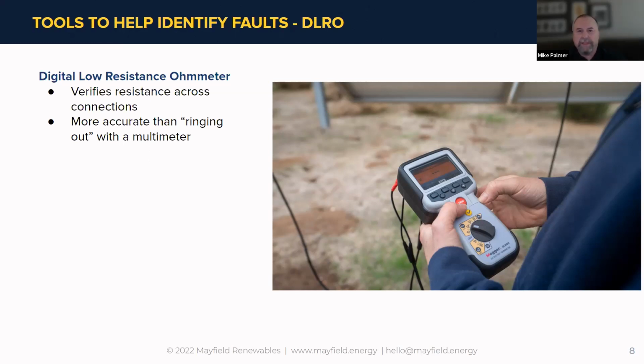And at the end of the day, it's really safety as well. But the other thing that affects these connections, I mentioned it earlier with the dissimilar metals, but we have temperature, we have the corrosion that occurs. We've pretty much hit it all on what the low resistance test will do. But there again, we have 2 amps, 10 amps, 100 amps, 200 amps, up to 600 amps. We're not using that, of course, on such small connections, but we use what's needed to tell us a historical measurement from commissioning, and just so you know, commissioning could be 10 years later because you never did it the first time. It could be today, and it could be 10 years later today. And that's our line in the sand that we're going to start at to test these connections.